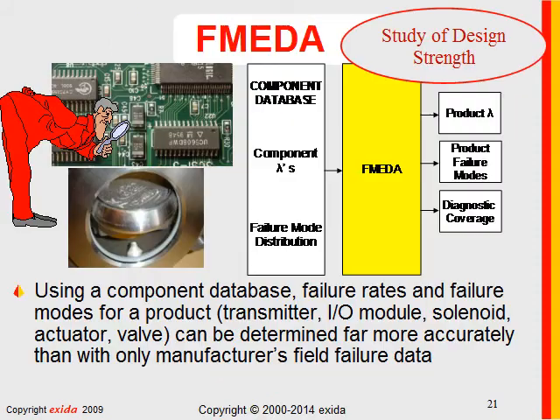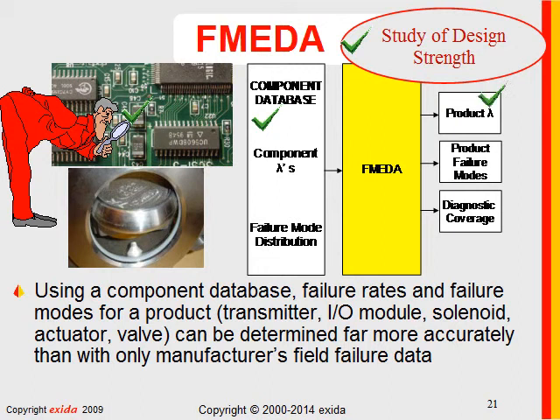FMEDA is truly a study of design strength — a tedious process that not everyone enjoys. Every single part is reviewed: if this part fails in this mode — for example, if a capacitor fails open circuit — how does that impact the design? Does the device continue to operate, fail safe, or fail dangerous? Can the diagnostics detect that failure? Using a component database with failure rates, failure modes, and useful life, the FMEDA process generates product failure rates, failure modes, diagnostic coverage, and even useful life.